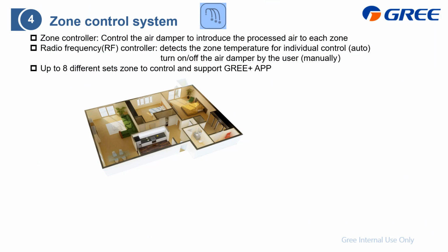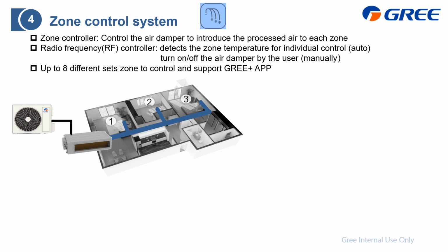Zone control system. This one is similar to VAV, short for Variable Air Volume system. And here is how it operates. For example, this is an apartment. There are some rooms, and it has already installed the UMatch with the duct type, and here is the air ducting. For every room, there is an air damper to control whether this room requires the cooling load, which means if we require cooling, basically we will turn on this air damper and then we can get the air, or we can get the capacity from the duct type.